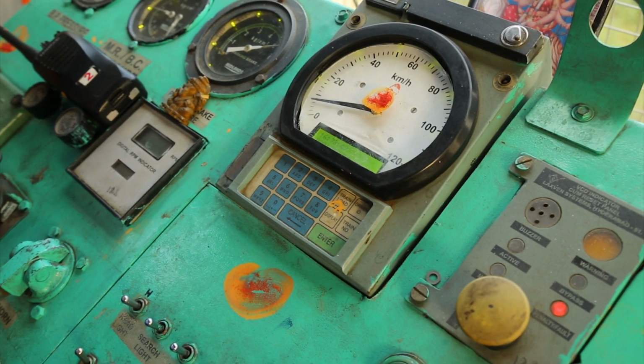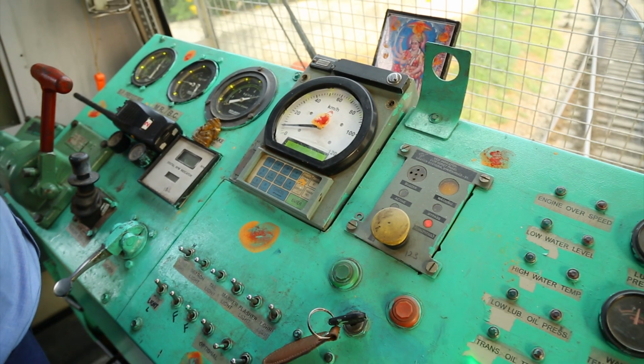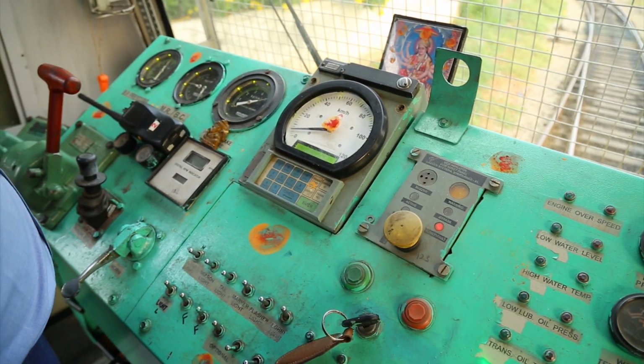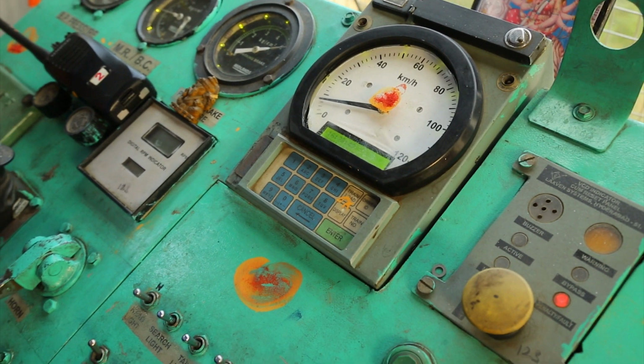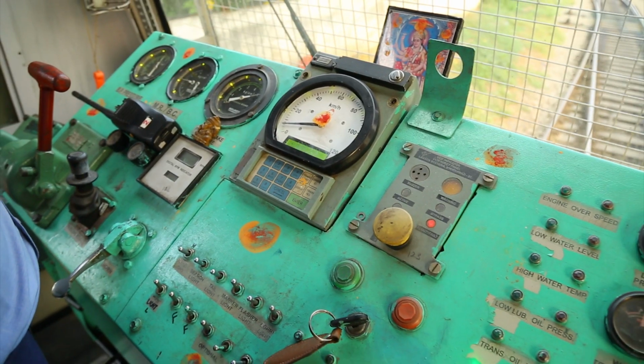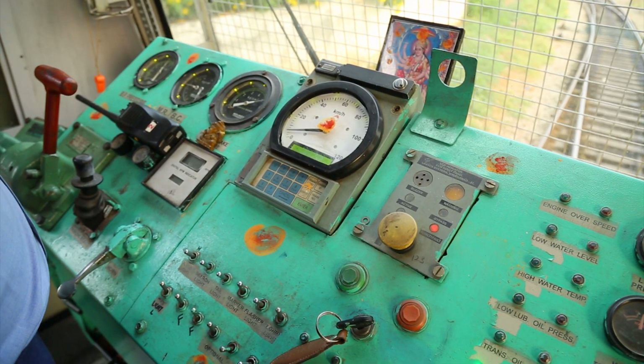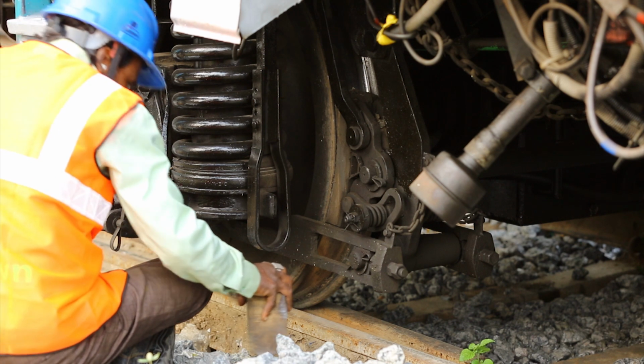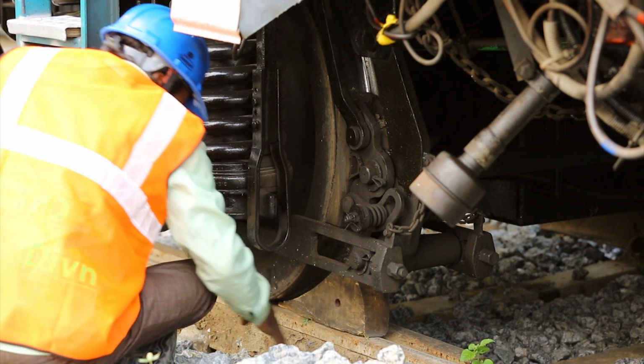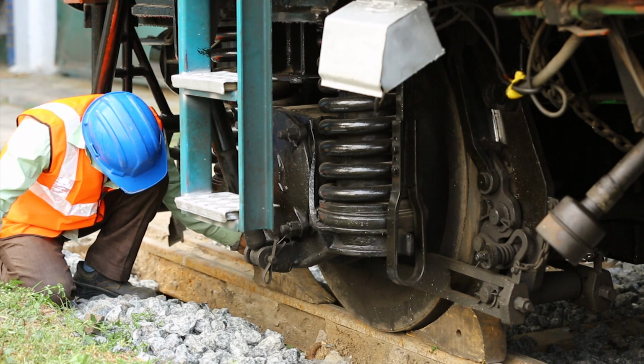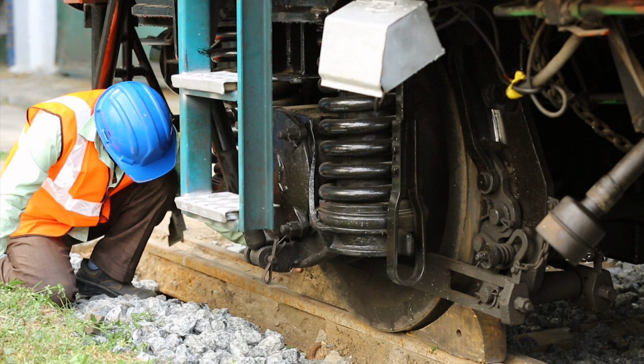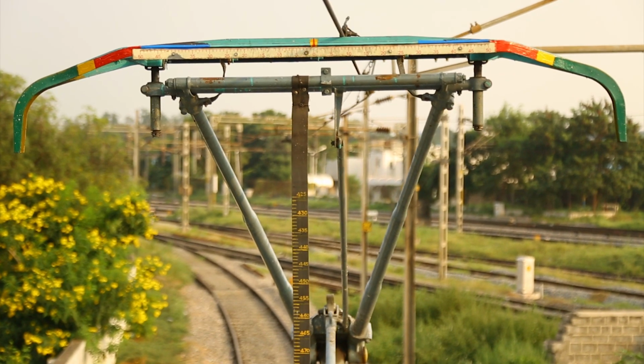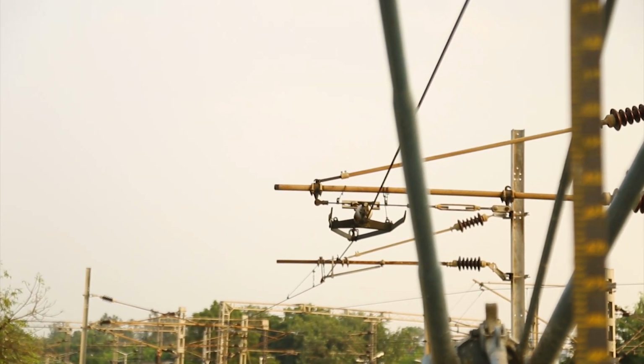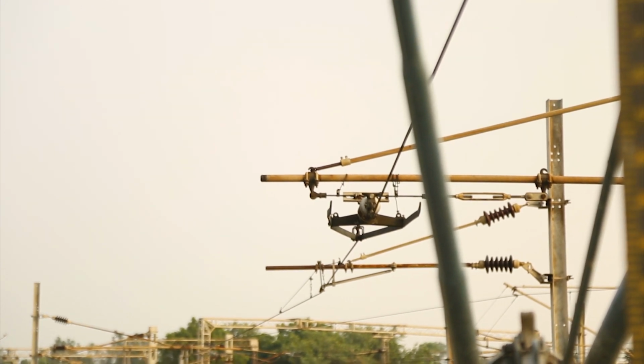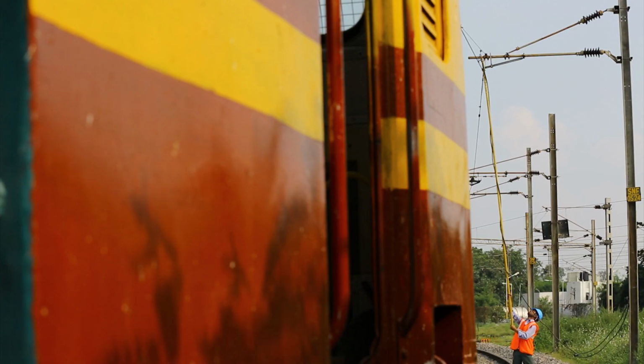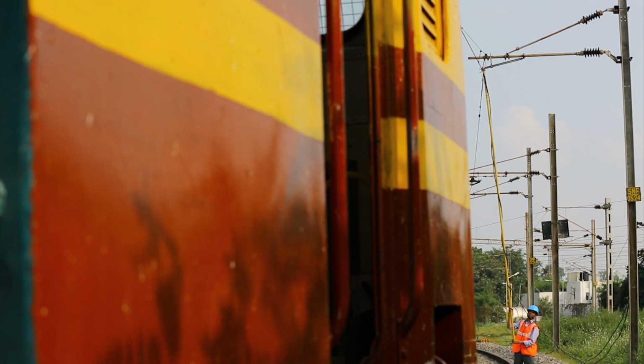Tower wagon shall be driven at a speed not exceeding 10 km per hour when checking contact wire level and stagger. If the tower wagon is driven for other than recording operations, the speed should not exceed the design speed, subject to the speed restrictions imposed in the section. Ensure that wooden wedges are provided at both sides of tower wagon wheels during stationary condition, along with handbrake or parking brake applied. Driver shall always stop the tower wagon ahead of all turnouts, crossovers, insulated overlaps and section insulators first, and then proceed only after ensuring that the section ahead is dead and earthed.